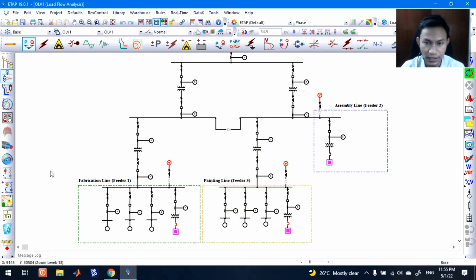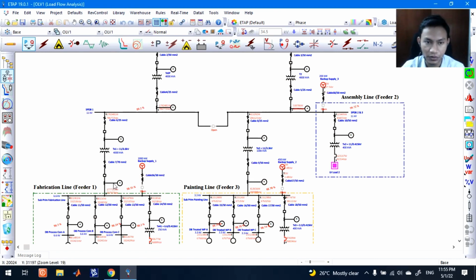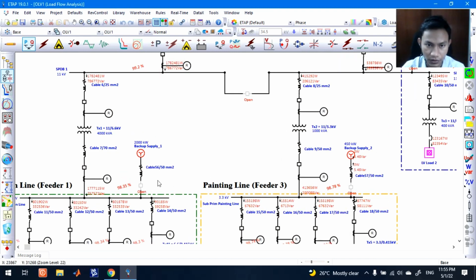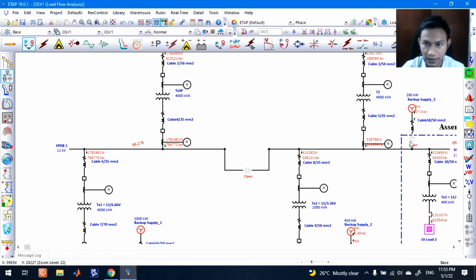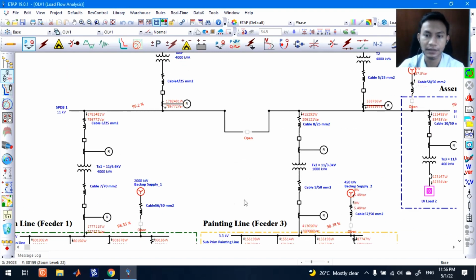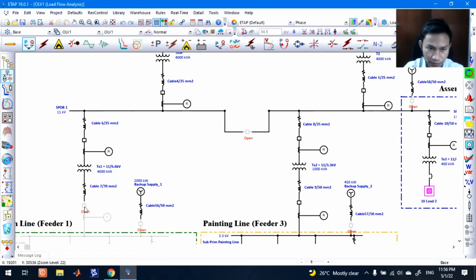My group was thinking about how to get a solution, a backup solution. We think we need to put 3 generators for the 3 feeders, which are feeder 1, feeder 2 and feeder 3. So what you can see here, I open this breaker, and also this one, and this one. These 3 are the backup supply, which are the generators. Okay, if I open the 3 breakers, you can see.